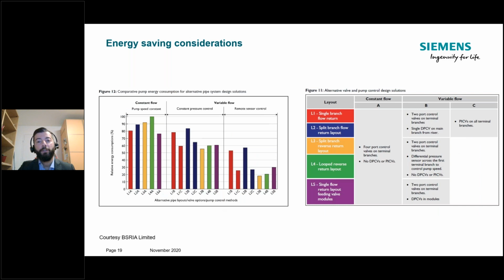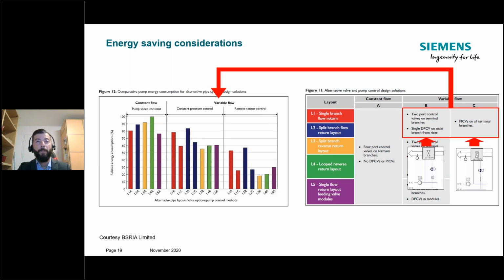So once we understand what is done, we can now check what happens to the energy consumption of the pump if you use traditional valves or PICV with the various pump speed control strategies. In the first case, with the constant pressure control, we can see the saving goes close to 25% when you switch from a static control to PICV. But if you look at the remote sensor speed control strategy, then the saving goes even beyond and reaches a relevant amount of 50%.